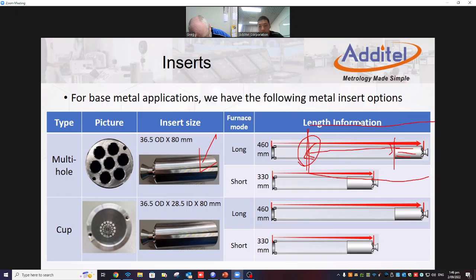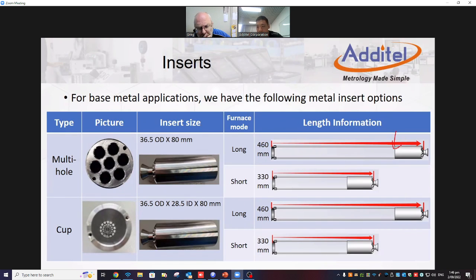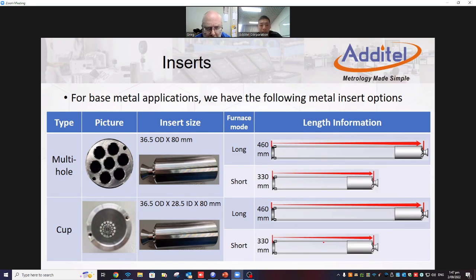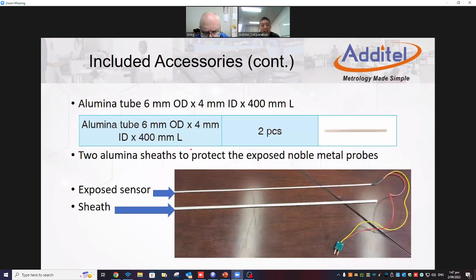So for example, we may have 1000 degrees Celsius right here. Here's the end of the furnace. We may have 990 right here, 990 right here, but starting here, that'll be 1000 again. That means we have enough length with the high, stable temperature right here, so we don't need to worry about the gap between the probe and hole. This is a really good question. And this is also the reason why the horizontal furnace is better, because we don't need to worry about the hole size.